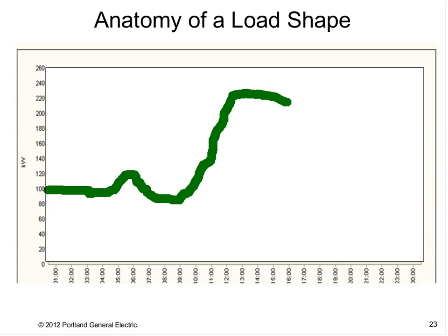And then around 3, 4 o'clock, you get a little dip upwards for the chiller that just came online. And then around this time, people start leaving, and load drops off back towards your base load of 100. And then from there, during the nighttime, you got your outdoor lighting that comes on, and then your janitorial staff leaving. So that would pretty much be the look of my building's load shape.